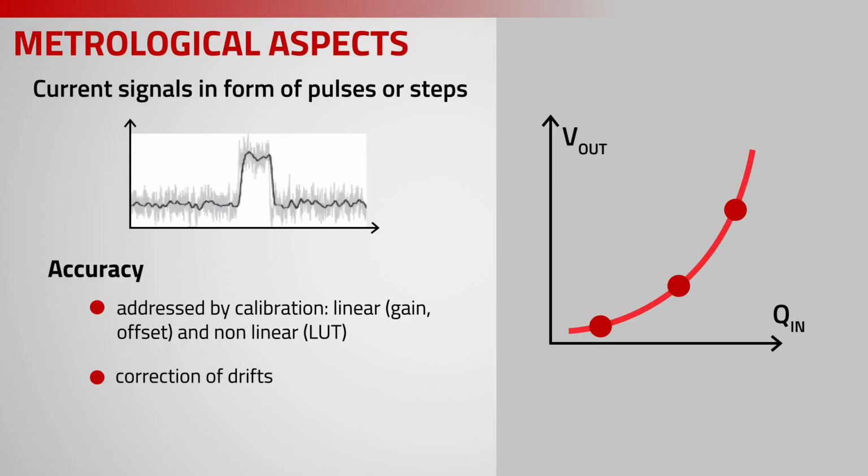It is important to keep under control cross-sensitivity to temperature or other effects, and also, in the case of multi-channel systems, to control crosstalk among parallel channels, especially in high-density implementations.